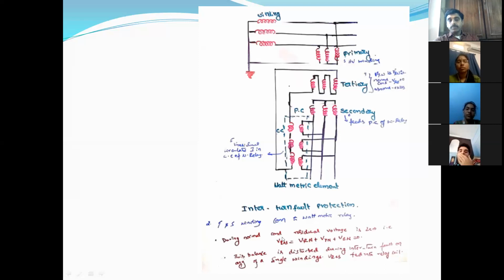Residual voltage means the sum of all the phase voltages, which is 0 under normal condition. Whenever there is a turn to turn fault, there will be a residual voltage. So this scheme is based upon residual voltage identification. When there is a residual voltage, that voltage will be given here. That means that residual voltage will circulate current in the current coil of the wattmetric relay. This is the wattmetric relay. The wattmetric relay contains current coils as well as pressure coils. Here there are 3 current coils and 3 pressure coils.